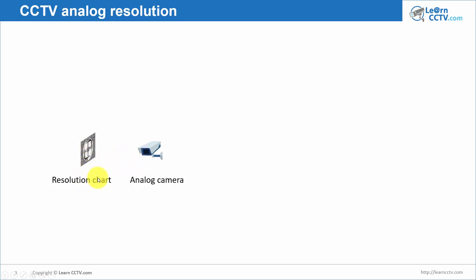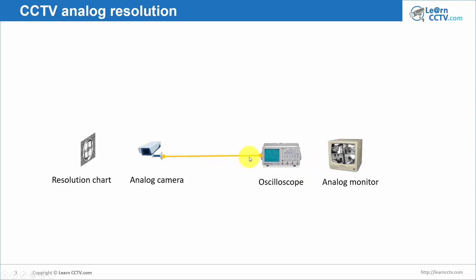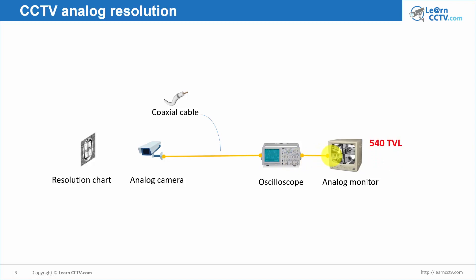In the past, you used to measure analog resolution like this: you have a resolution chart and an analog camera, and then you have an oscilloscope and an analog monitor. You connect a coaxial cable from the camera, and also a coaxial cable from the oscilloscope to the analog monitor. The idea is that you can measure the resolution of the camera using an oscilloscope in a lab setting. You're going to find if the camera is 540 TV lines, 600 TV lines, 700 TV lines, or whatever resolution the camera has.